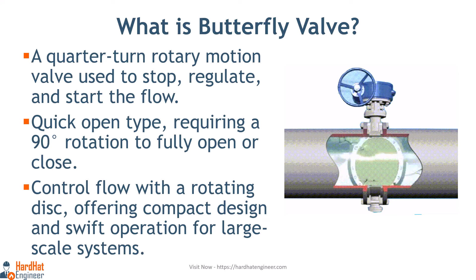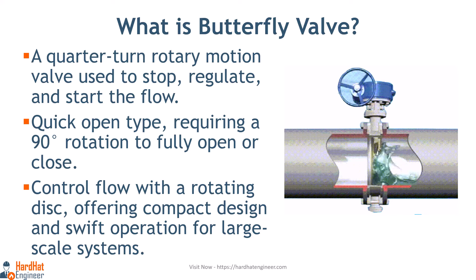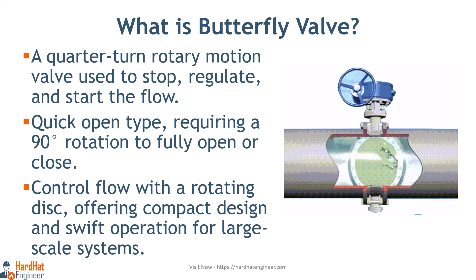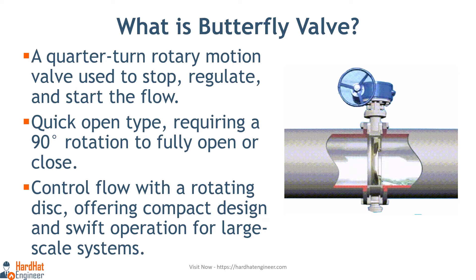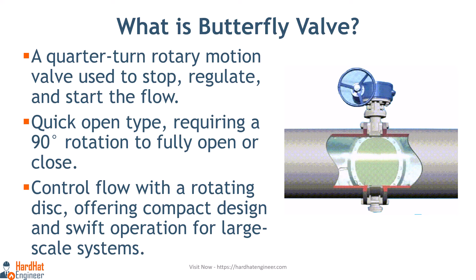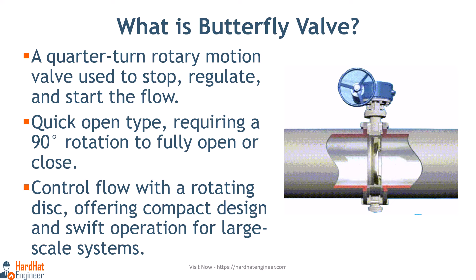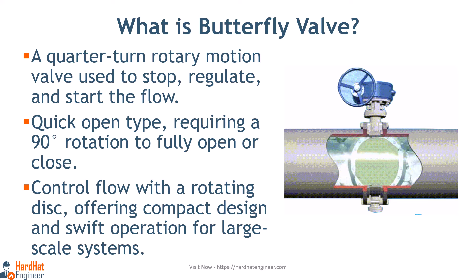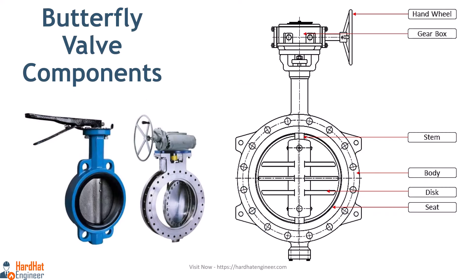What is a butterfly valve? Butterfly valves control flow with a rotating disc, offering compact design and swift operation for large-scale systems in industries. It is a quarter-turn rotary motion valve used to stop, regulate, and start the flow. Butterfly valves are a quick-open type — a 90-degree rotation of the handle can completely close or open the valve. Normally they are used in systems where a positive shutoff is not required.